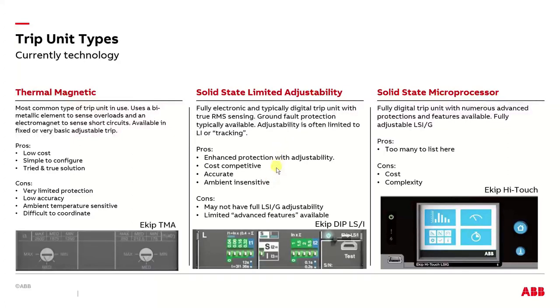So you can get a solid state or electronic trip breaker that's simple, that's very cost competitive with thermomagnetic, and really that's a big improvement. In places where you have larger breakers, that cost might be zero, or we may only be able to get solid state. So the protection is getting better per dollar with your solid state breaker.